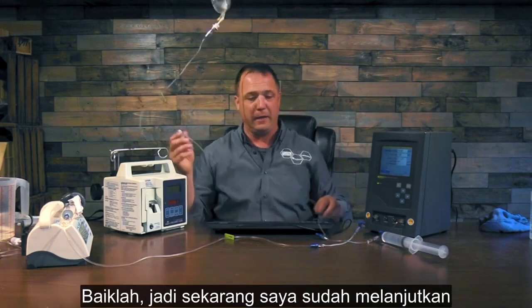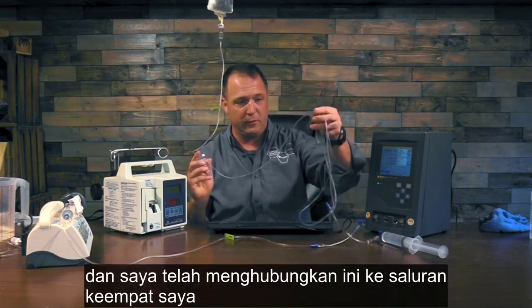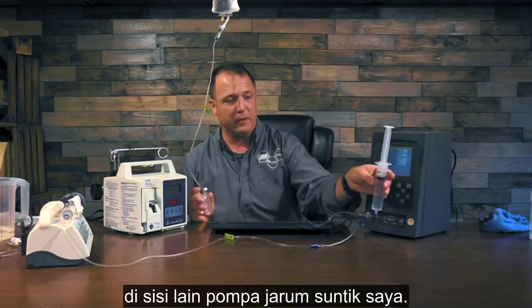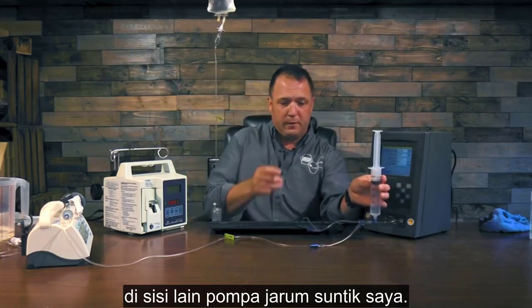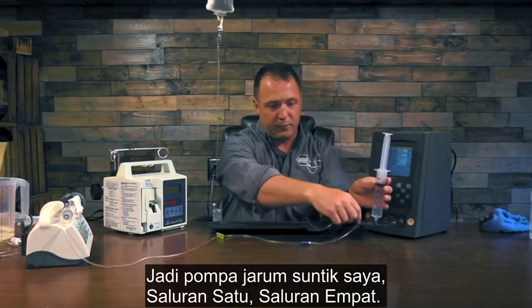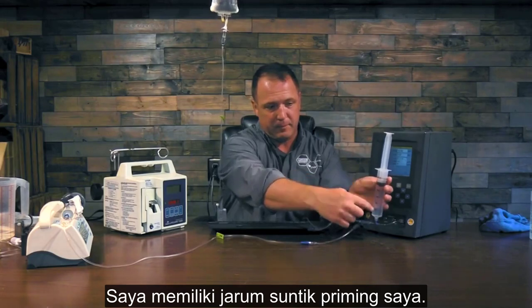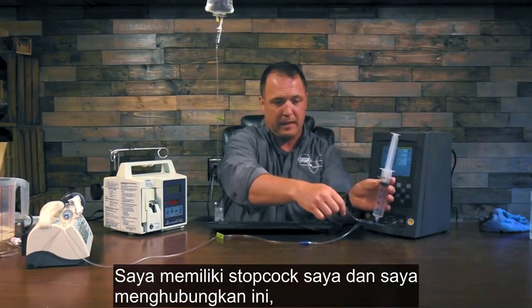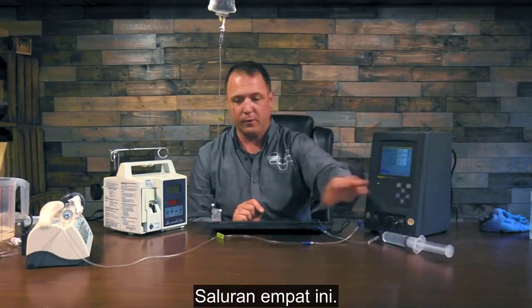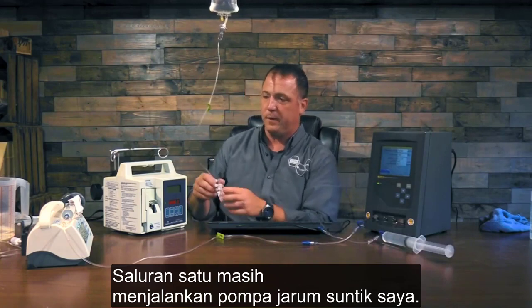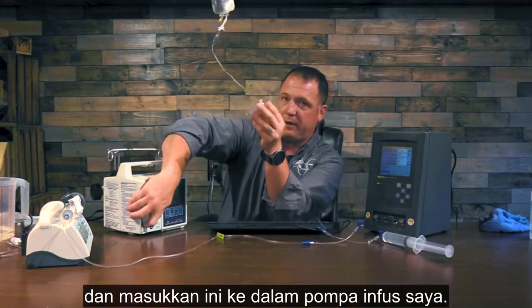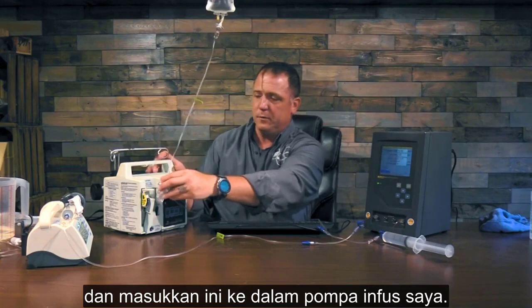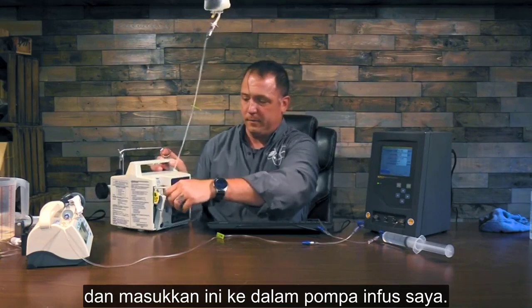Alright, so now I've gone ahead and I've hooked this up to my channel 4 on the other side of my syringe pump. So my syringe pump is channel 1, and on channel 4 I have my priming syringe, I have my stopcock, and I have this connected in. It's channel 4, with channel 1 still running my syringe pump. And I'm going to go ahead and put this into my infusion pump.